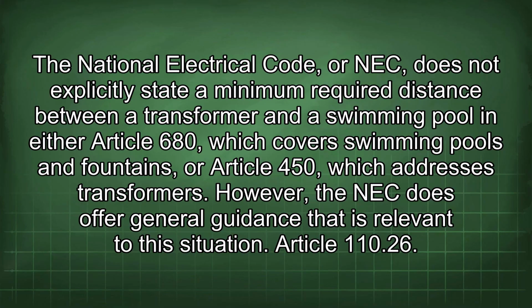The National Electrical Code, or NEC, does not explicitly state a minimum required distance between a transformer and a swimming pool in either Article 680, which covers swimming pools and fountains, or Article 450, which addresses transformers. However, the NEC does offer general guidance that is relevant to this situation.